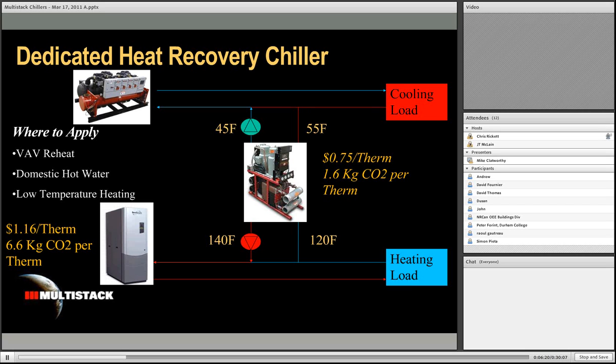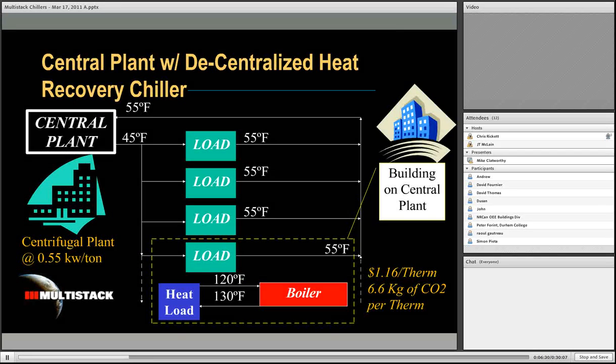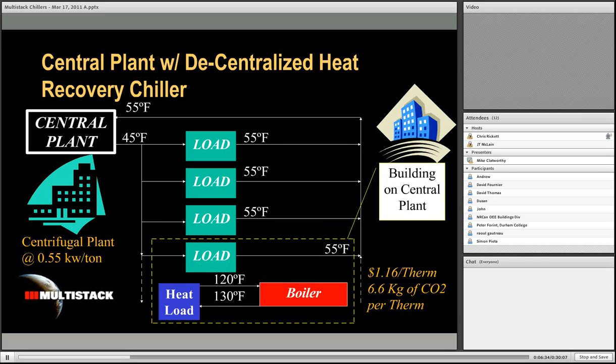So it's actually a very simple concept. That chiller, that dedicated heat recovery chiller, hopefully that doesn't sound too oxymoronic, but that's really what we're doing. We're chilling water and we're heating water. That chiller is sized to the simultaneous heating and cooling loads.